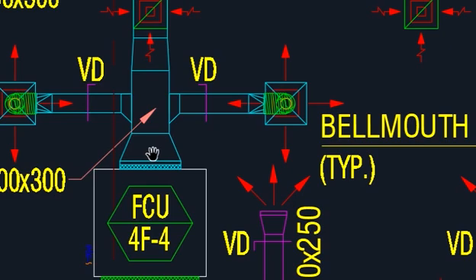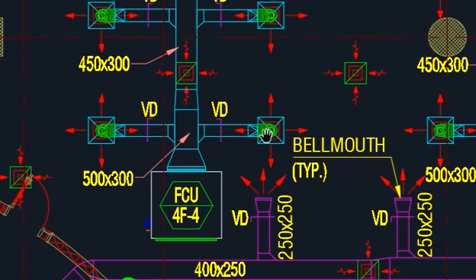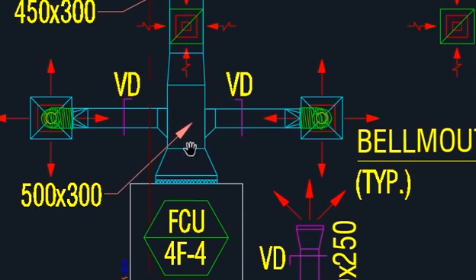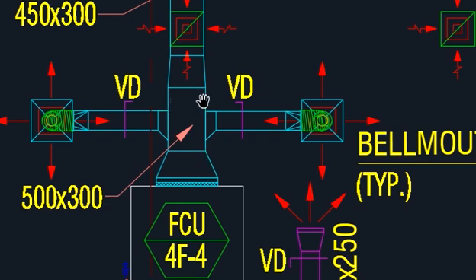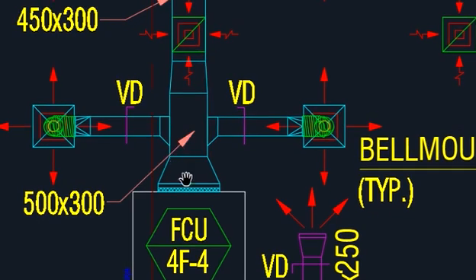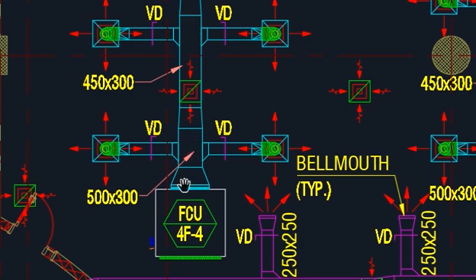The acoustic lining duct must be installed. The purpose of the acoustic lining is: when the air is pushed inside by the blower, the airflow toward the grills will create sound. So the acoustic lining eliminates the sound — it is like a silencer, like the silencer on motorcycles or cars. Inside the duct, there is a special material — like a small mesh or jali — that eliminates the sound. So from the FCU, two branches go out, and one meter of acoustic lining duct with reducer must be installed to eliminate the sound.